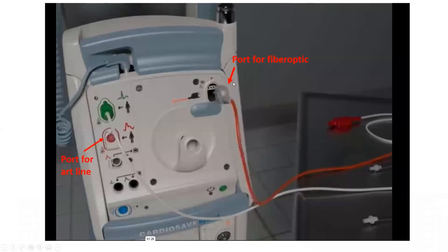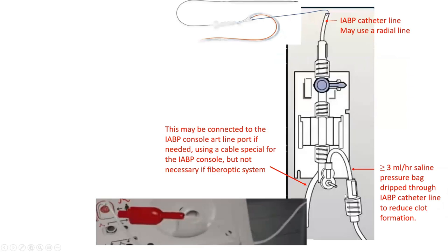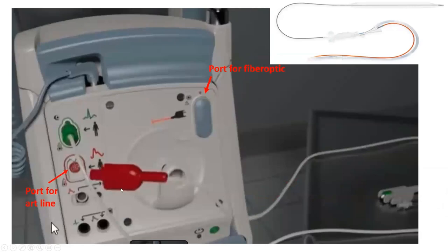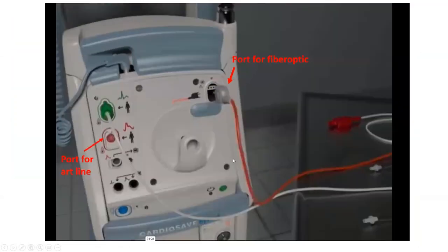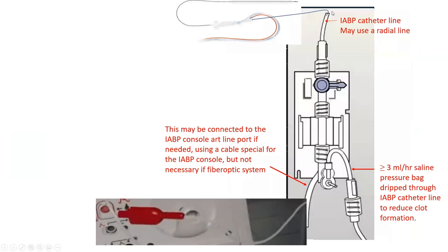In those cases, if you have a fiber optic, maybe your fiber optic is dysfunctional. You need to use, like I explained, your arterial lumen. Connect your arterial lumen, which is already connected to a heparinized saline bag and to a transducer. Connect that transducer via a special cable to the back of the balloon pump and monitor via it. If your arterial lumen is clotted and you didn't have fiber optic, you only had the old-fashioned balloon pump with arterial lumen, what you can do is connect that cable and the transducer to a radial arterial line or a femoral arterial line, and connect it to the back of the console.